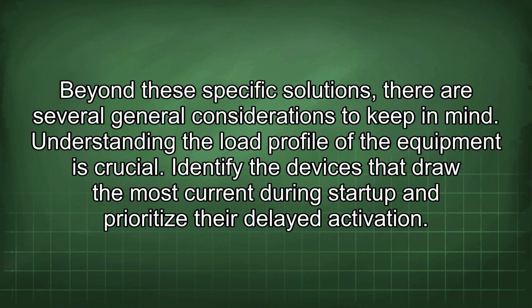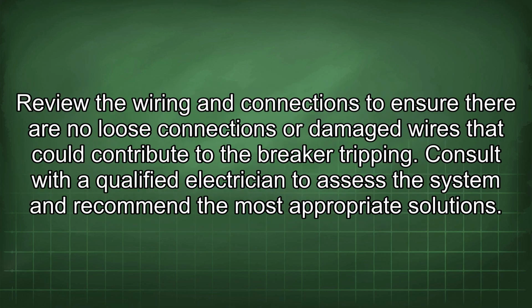Beyond these specific solutions, there are several general considerations to keep in mind. Understanding the load profile of the equipment is crucial. Identify the devices that draw the most current during startup and prioritize their delayed activation. Review the wiring and connections to ensure there are no loose connections or damaged wires that could contribute to the breaker tripping. Consult with a qualified electrician to assess the system and recommend the most appropriate solutions.